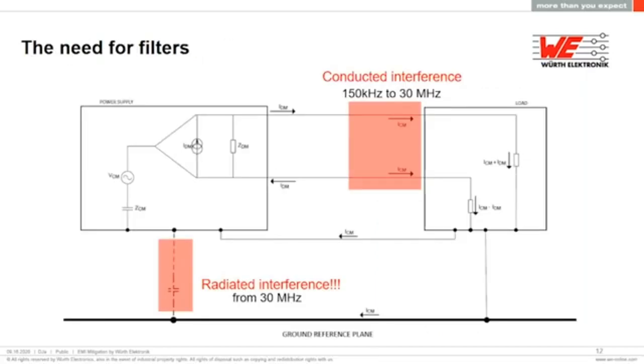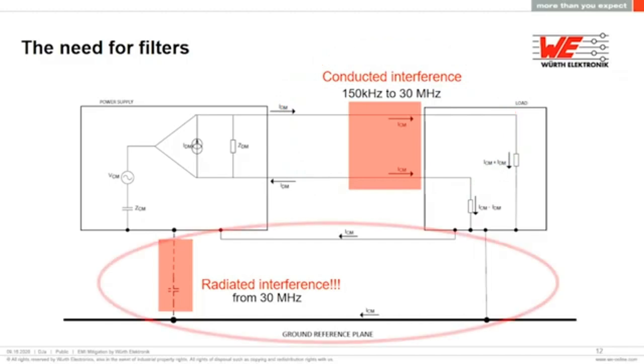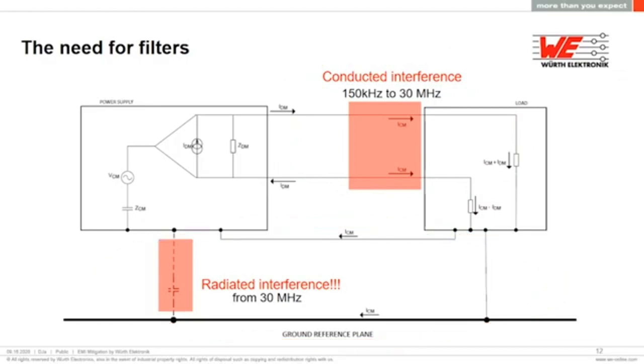EMI is defined as unwanted signals and can be in the form of conducted or radiated emissions. Conducted EMI is where the noise travels along electrical conductors, and radiated EMI is where the noise travels through the air as magnetic fields or radio waves. Conducted interference is measured from 150 kHz to 30 MHz, but for radiated it's over 30 MHz.